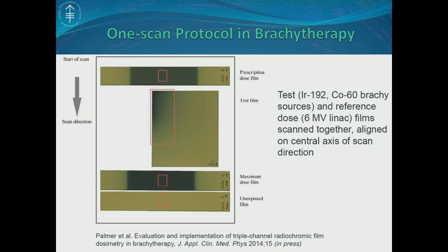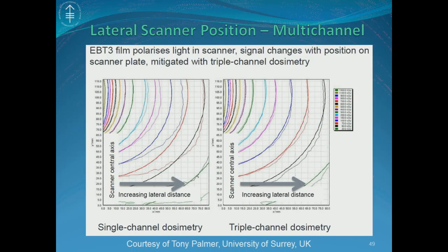Remember, the reference dose can be from a 6 MV LINAC because EBT3 film is nearly energy independent in the therapeutic dose range. As you can see, the scan direction is always along the long side of the scanner, and the region of interest should be located in the central area of the scanning window. This shows the lateral response artifacts for both dosimetry methods. This is important because the QA film is positioned toward the right side of the scanning window. So the triple channel method gives a better result than the single channel method.